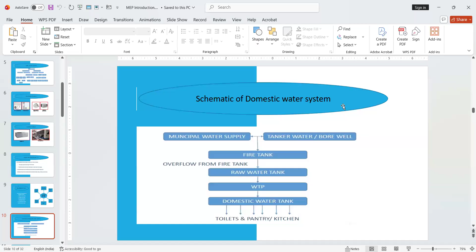Domestic water systems are mainly of two types: gravity and hydro pneumatic. In a gravity-based system, water is fed from the overhead tank through gravity, and to maintain adequate pressure, a booster pump is installed at roof level. If the building has three floors, the third floor may not get adequate pressure through gravity alone, even though the ground floor will. So a booster pump has to be installed for the third floor, while the second, first, and ground floors can be supplied directly through gravity.